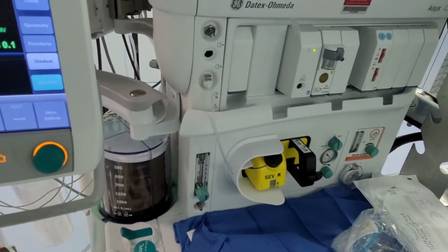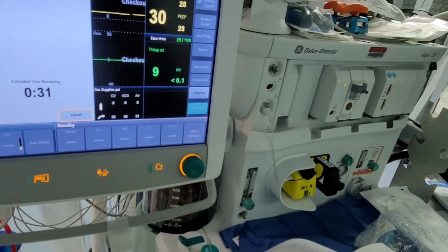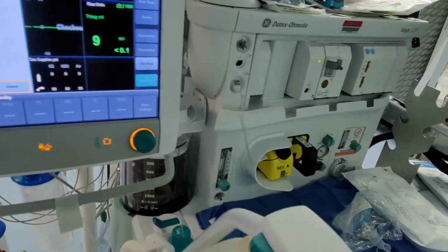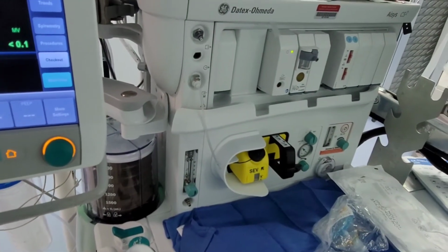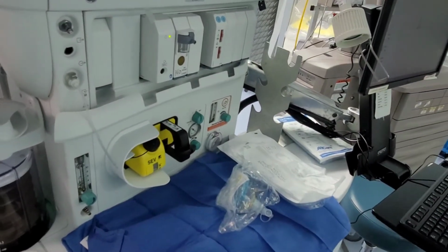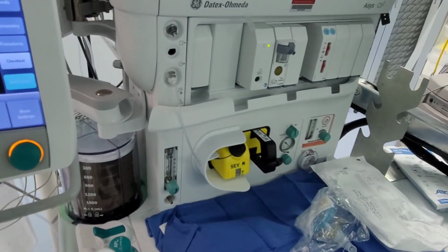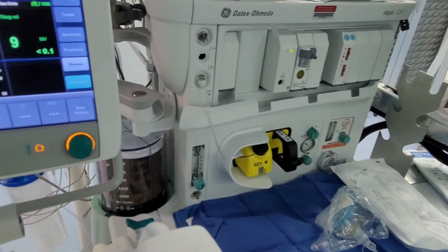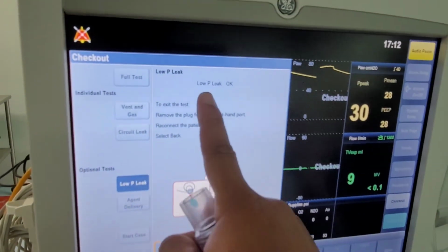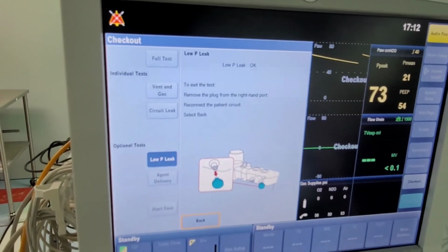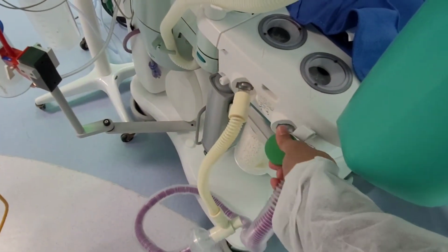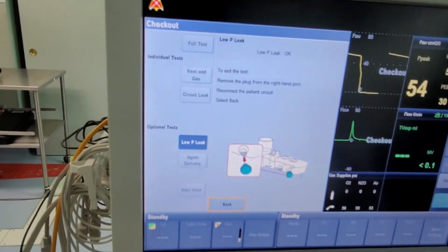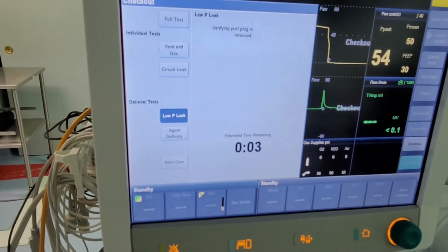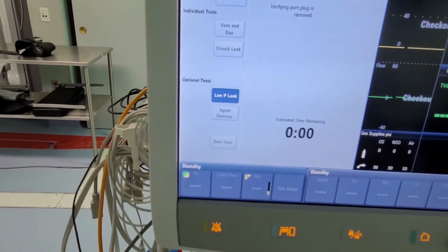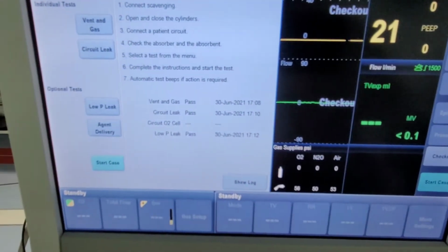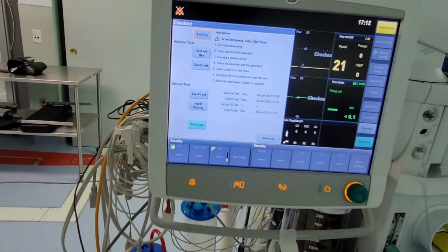This is similar to the Aisys CS2, Aestiva, and ADUs. The only difference is that the Aisys CS2 is automated. You don't have to open the vaporizer to 1%, 3%, 5%, as this one's completely electronically controlled. Once it's finished, it'll say low P leak OK, and you're instructed to take the plug off the right hand port. Take it off, which releases the pressure, press back as instructed, and it verifies that there's no occlusion and passes.